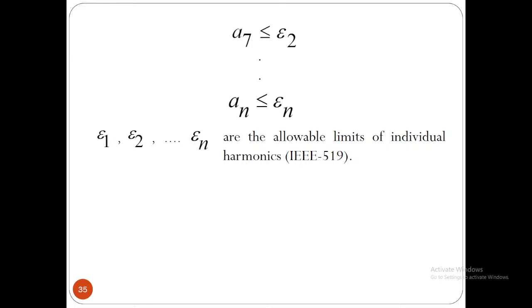Now this is the interesting phenomenon. We are not equating those harmonics to 0. We don't want to eliminate those selected harmonics completely. Rather, we are restricting them to a specific value. What are those values? E1, E2, E3. It's not E actually. Epsilon 1, these are the errors. So as per individual harmonics, as per IEEE 519, what is this? IEEE 519 is a code. This is made for your DG. This is an international standard set by the IEEE.